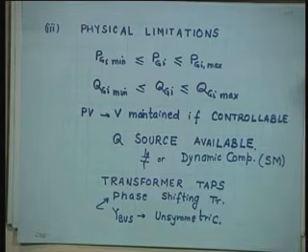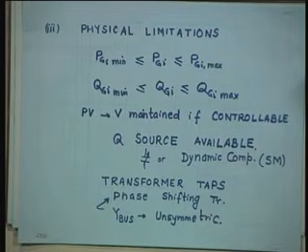In our country, near Kanpur, there is a Panki station. That is the only station where a static VAR controller is established, no other place, because it is very costly. And a dynamic compensator, all of you know, is a synchronous motor running at no load. A synchronous motor is the only motor which can operate at lagging power factor as well as leading power factor, whereas an induction motor always means lagging power factor.